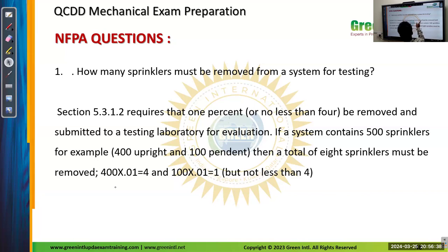But there is one more condition, not less than 4. Means in this type, you have to take 4. And in this type, you have to take 4. So total 8. So you have to remove 8 sprinklers, not 5 sprinklers. Okay. 2 conditions, you are taking the maximum of this. Yes. So we will take 4 plus 4, total 8.